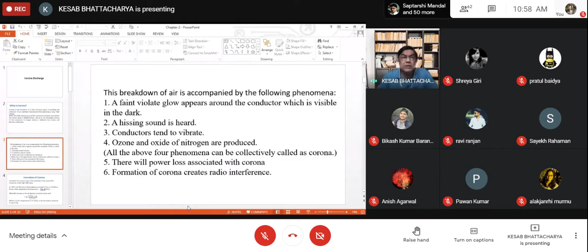And when corona is formed, due to ionization of air, some high frequency oscillations set in the system. Though it is not a permanent feature, when corona occurs, high frequency radiations are found to be occurring in the vicinity where corona sets in, and these high frequency radiations interfere with the radio waves, which causes enough disturbances in your system. So these are the phenomena which are associated with corona.